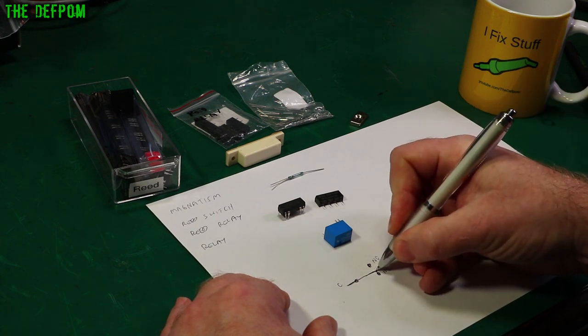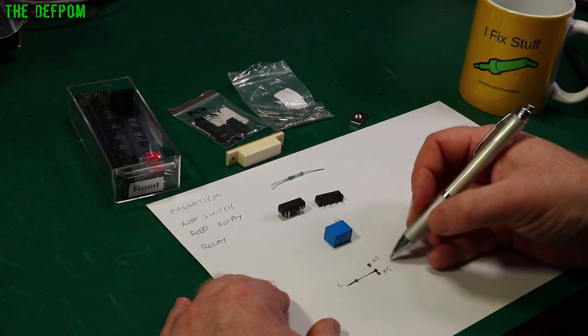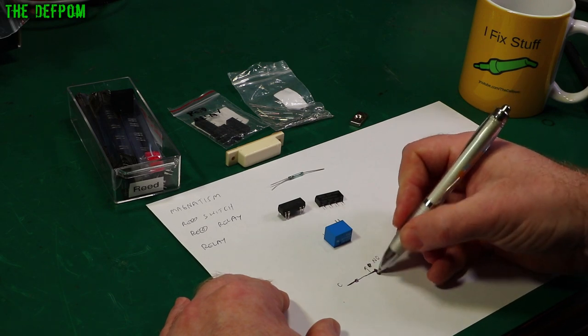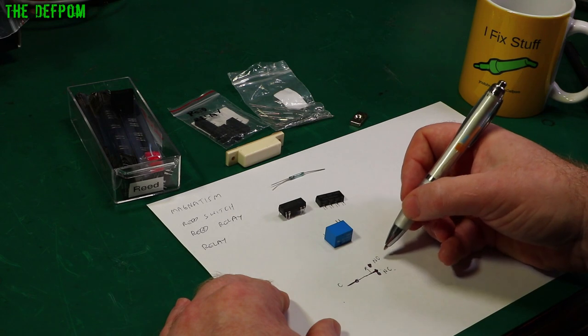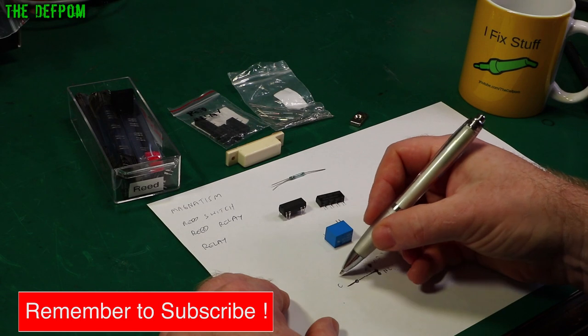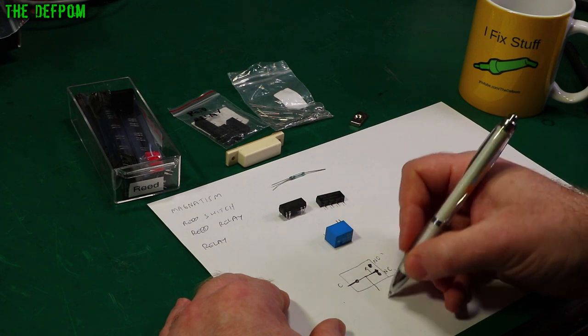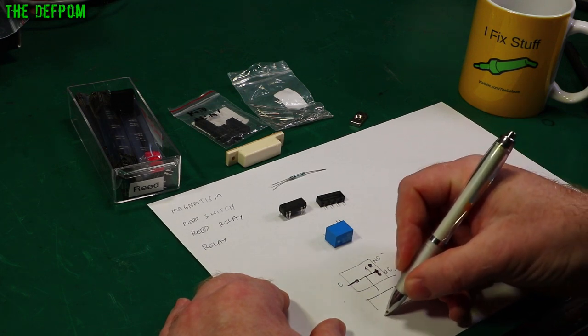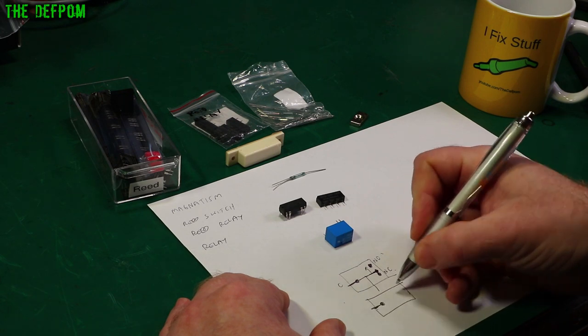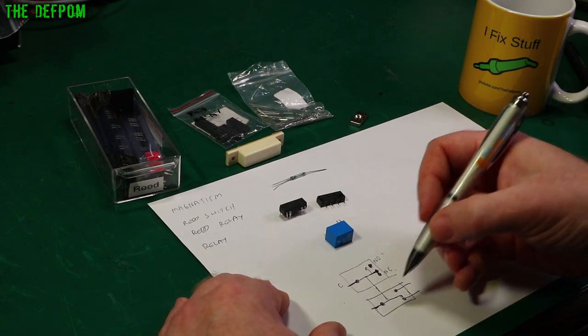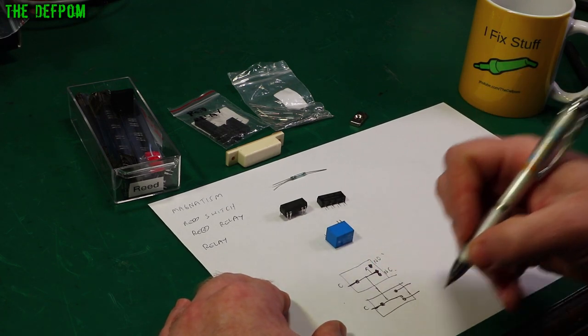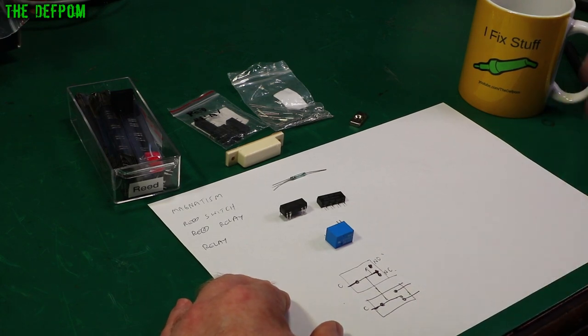Normally closed means you've got a connection point here. When it's de-energised, it's connecting through these pins. When it's energised, this moves over that way. It disconnects from this one, connects onto this one, and that then becomes closed instead. That is a single pole switch. But you can actually get a bank of these. Sometimes you get a bunch of them attached to each other. Same circuit duplicated across. Then that becomes a two pole switch, double pole. Then you can get triple pole or quadruple pole, depends on what you need.